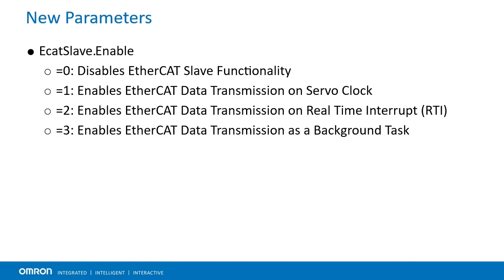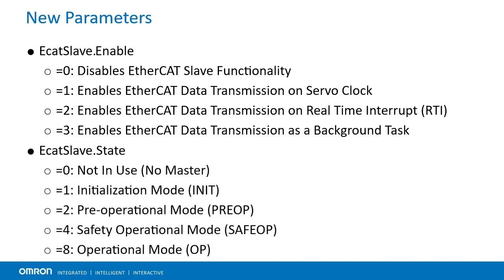A value of 3 means data transmission occurs asynchronously, not at a fixed frequency. Users will typically want to set this parameter in a header file in their project so that it is always on if they intend to use this feature. The next parameter is ECATSlave.State, which displays the current EtherCAT state of the device. A value of 0 means not connected or no master detected; 1 means initialization mode; 2 means pre-operational mode; 4 means safety operational mode; and 8 means operational mode.